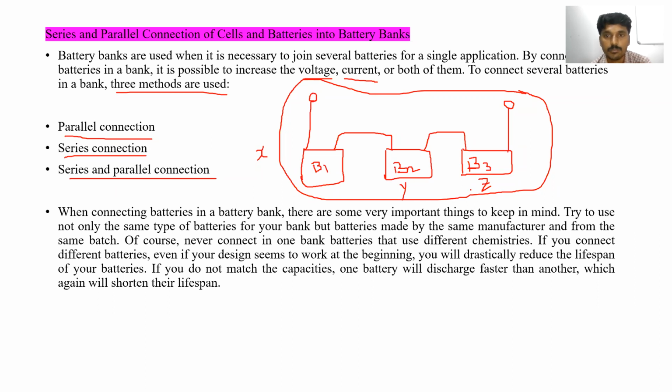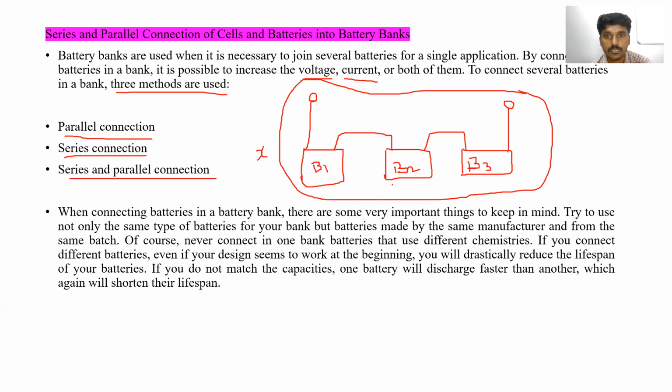All the batteries should be from the same manufacturer. Please remember, because if you take batteries from different manufacturers, different companies, then the chemical reaction is also different. Due to this, there is a chance to decrease the lifetime of the batteries, and there are also chances of damage.